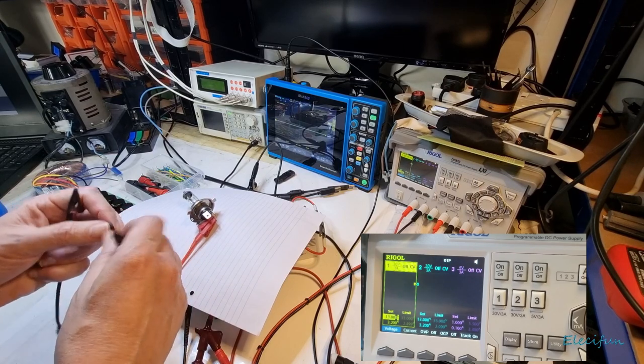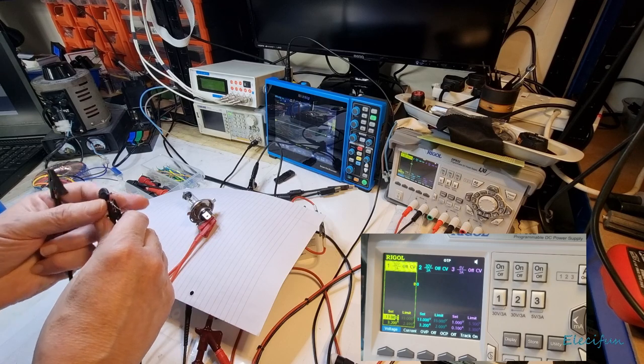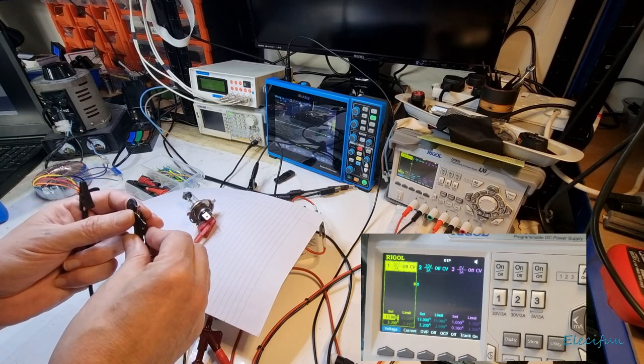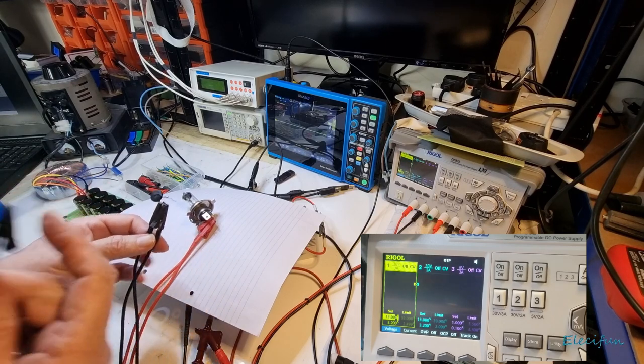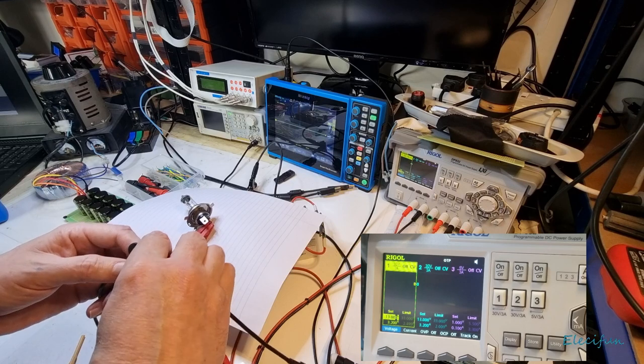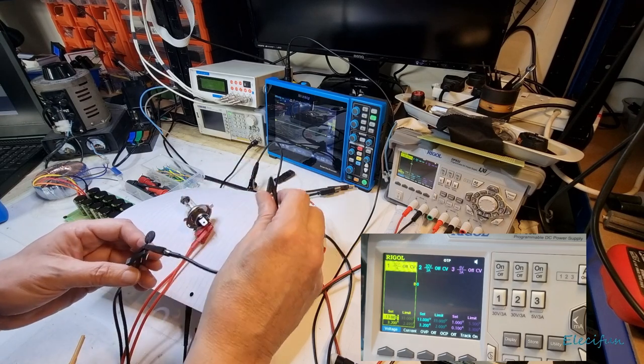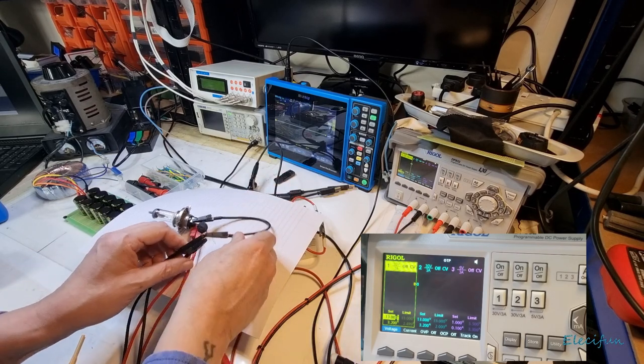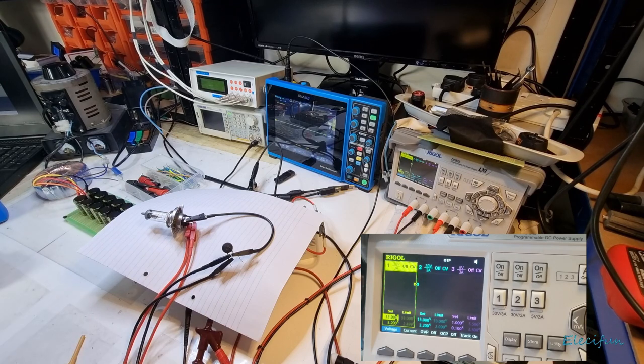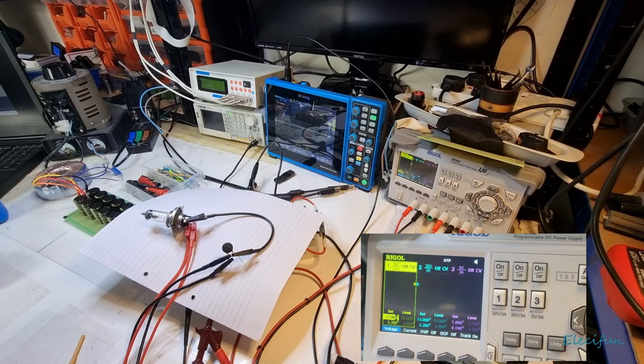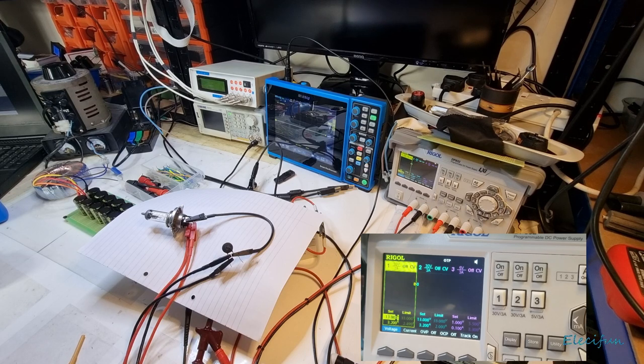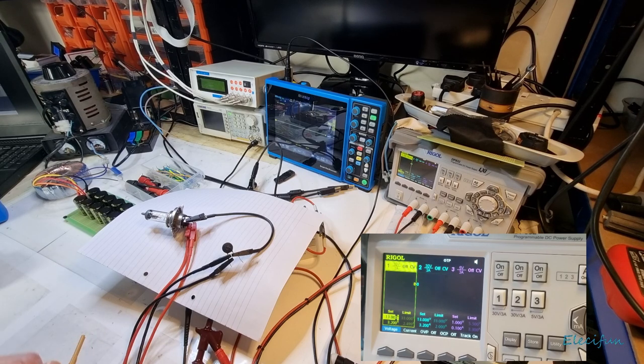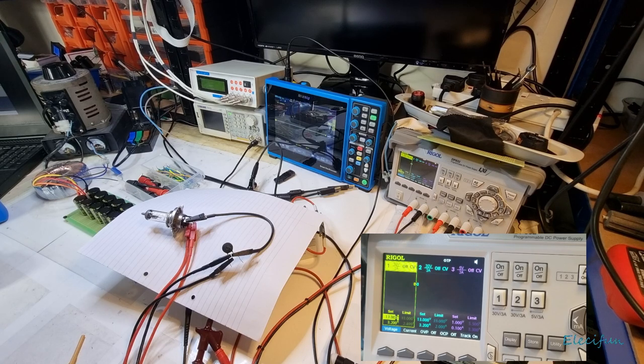And so that means that for that first little bit of time when that current is surging through, this thing's cold and it will prevent that current from surging through so fast. And then as time goes by and it starts warming up, that current, because the resistance will go down lower, will be able to flow a lot more freely. All it does is it just reduces that inrush and that's what you want.